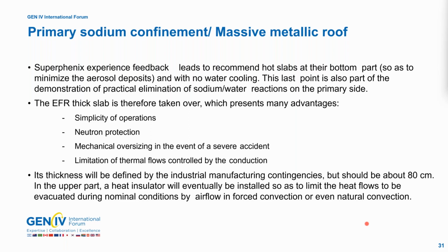huge, massive metallic roof. And we have a limitation of thermal flow because the thermal flow is by conduction, and the conduction is not efficient. And so we have a limitation of the thermal flow that is controlled by the conduction. The thickness will be defined by the industrial manufacturing contingency, but should be about 80 centimeters. In the upper part, we can add eventually a heat insulator to limit the heat flow to be evacuated to a nominal condition, but this heat flow should be evacuated by natural convection.